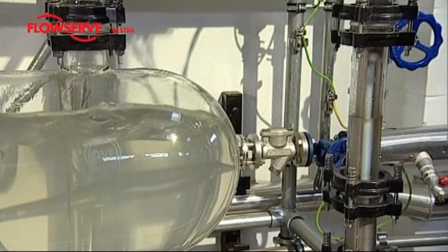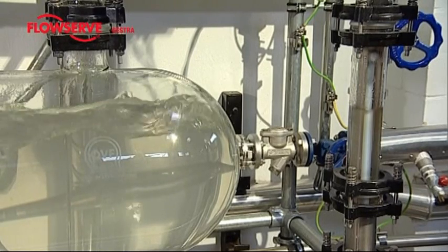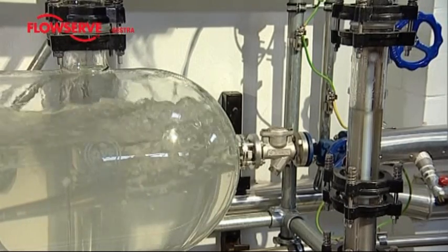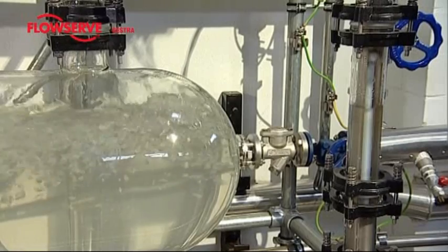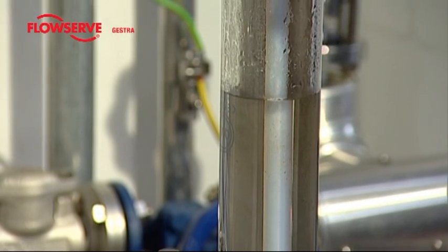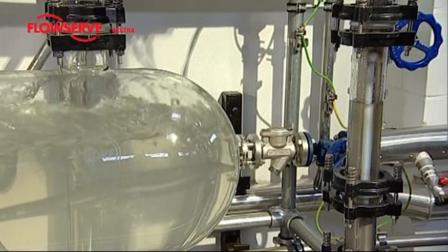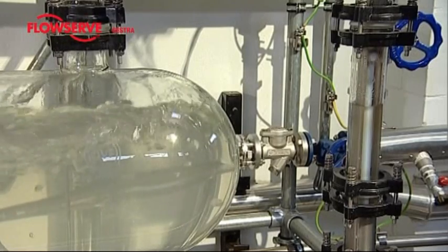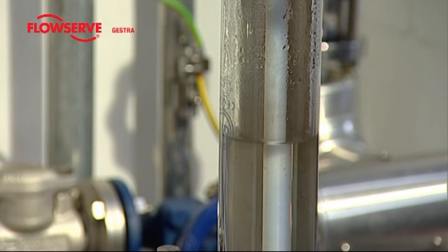Let's now try something else. Once again, the safety valve is opened, but this time is to simulate the effect of connecting major steam users to the system. Through the increased steam consumption, the pressure in the system falls. Right away, steam bubbles form everywhere in the boiler water, this being triggered by the pressure drop and the surplus heat or enthalpy. Through the sinking pressure, the area loading on the individual steam bubbles in the water is reduced, so that these occupy a greater volume, lifting the water level as a result. This effect can also be observed in the external measuring pot. Indication errors cannot be excluded.